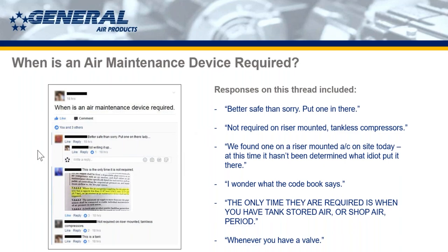So the woman who asked the question, when is an air maintenance device required, got a variety of answers. Like I said, better safe than sorry, put one in there; not required on riser mounted tankless compressors; we found one riser mounted air compressor on site today, at this time it hasn't been determined what idiot put it there; I wonder what the code book says; the only time they're required is when you have tank stored air or shop air, period. So, like I said, none of them are quite right. Some of them are funny. So let's clear it up here.